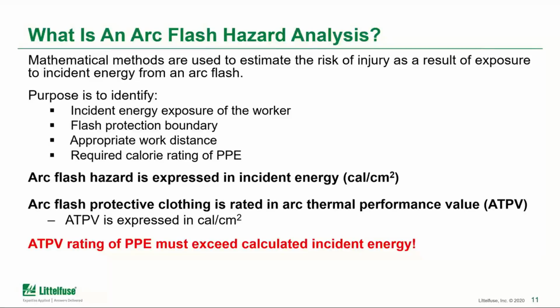And your PPE, so your arc flash protective clothing, is also rated in calories per centimeter squared. That one is given a name that's shown on the screen there, the ATPV, the arc thermal performance value, sorry. And of course, you want to make sure that your PPE rating is sufficient to protect you from the actual arc flash incident energy rating from that particular piece of equipment.